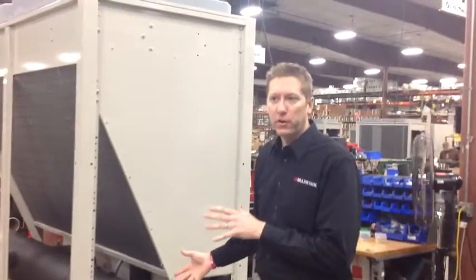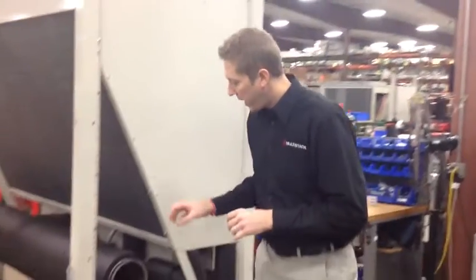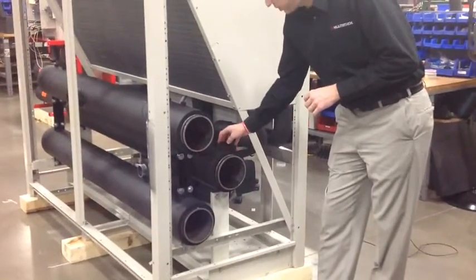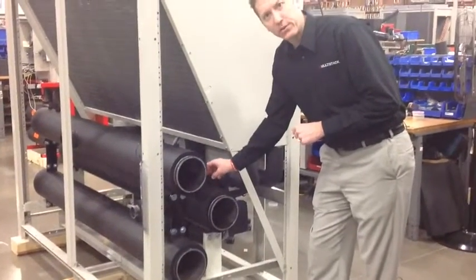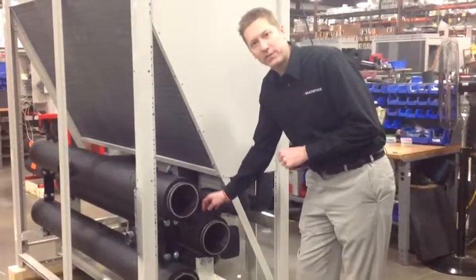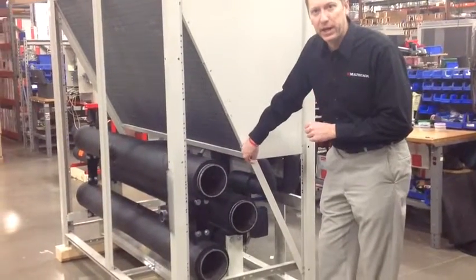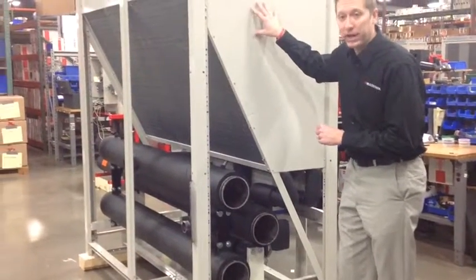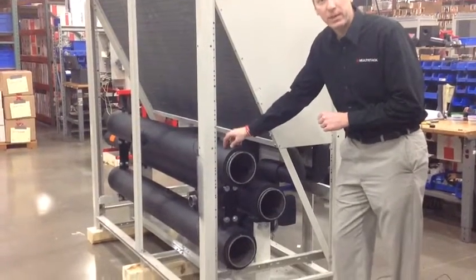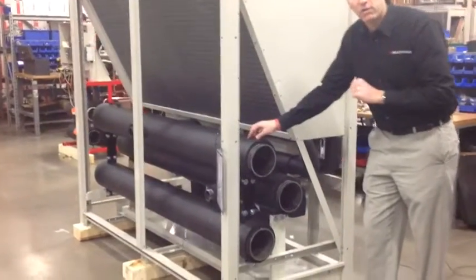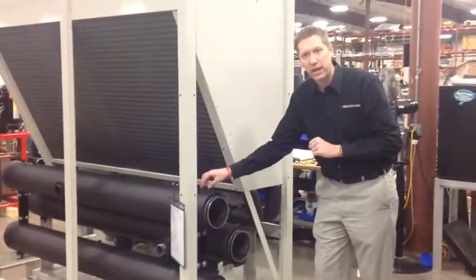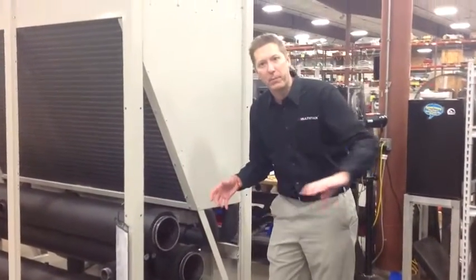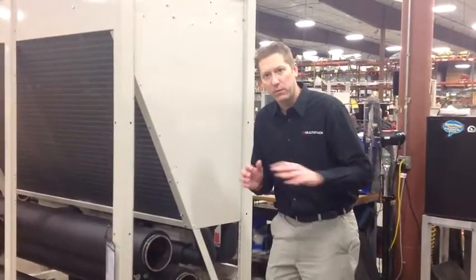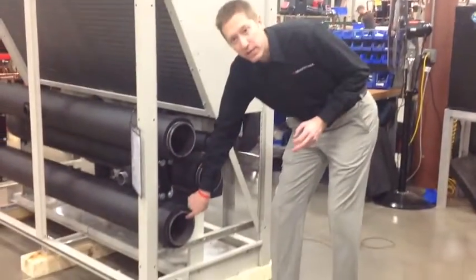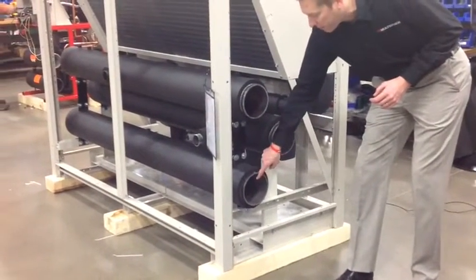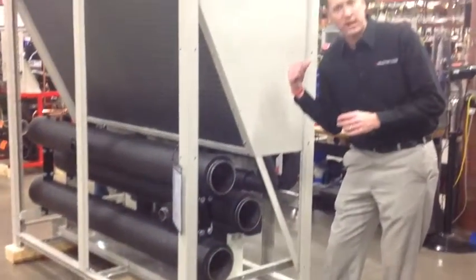Alright, so here we have our free cool module. This will be added on later. We have an entering free cool header. So we'll notice 3 headers here. That's because the free cool is in series with mechanicals, so this is our entering free cool header. Takeoffs will be used to get water, or glycol, to the coil, and we'll dump into this top header. So that is why we see the jog over on the pump skid, which is for getting to the top header. That is where the water will meet up and continue on into the mechanicals. They will do their work, and then they're leaving on the mechanicals is here, which is the bottom header on that pump skid, which ends up being the leaving going back to the building.